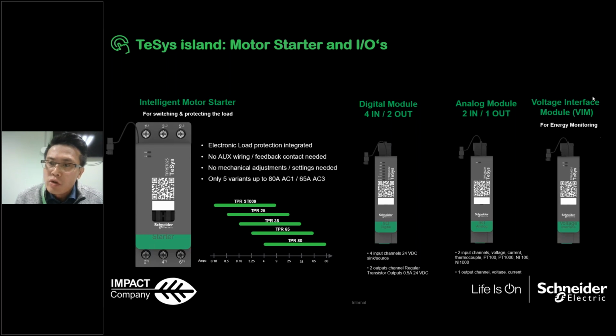We also equip a voltage interface module that measures the actual voltage. Basically, we measure the actual voltage of the system. We are not assuming the system voltage is 230 or 220. We measure the actual voltage. And then with the actual voltage, we also measure the actual current of each individual starter, of each individual contactor. That means now we have the actual voltage and the actual current, so that's why we can have the actual energy consumption of the individual load. So it is not assuming the voltage is 230 and then calculating the energy consumption, which is something like the other manufacturers do. But for us, we are measuring the real voltage and current to have the actual energy consumption of the individual load.